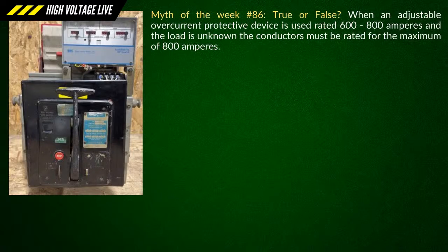But anyway, this is an adjustable breaker. It's adjustable from 600 to 800. What a lot of guys mess up is they size for the minimum, sizing for the 600, and then all of a sudden they have to change that breaker capacity to like 620 before they do a load calc or something. Then they have to eat crow and realize that they sized the equipment ground conductor wrong. That's the kind of thing we're trying to help you guys avoid in the future.